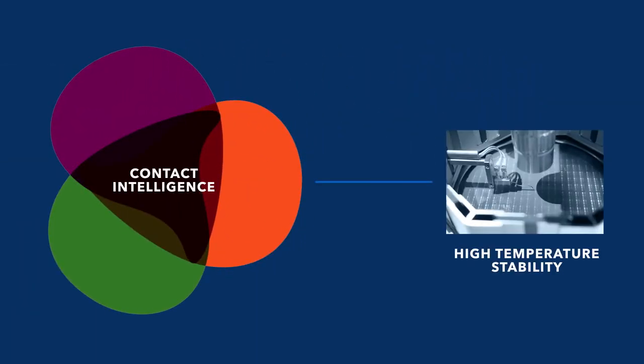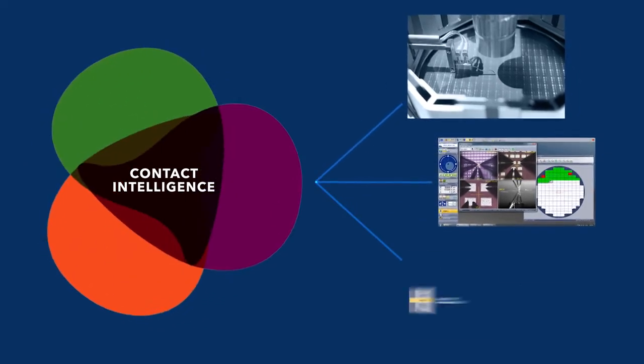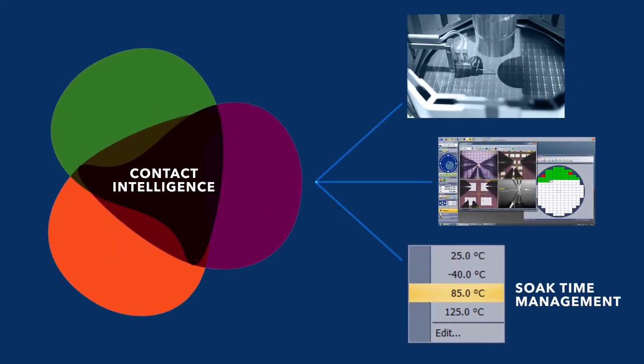We've combined high temperature stability hardware to provide accurate probe-to-pad alignment on 30 micron pads with on-axis probe-to-pad alignment at multiple temperatures using our ViewTrack digital microscope software. And, soak time management software automatically calculates the required soak time when moving from one temperature set to another.